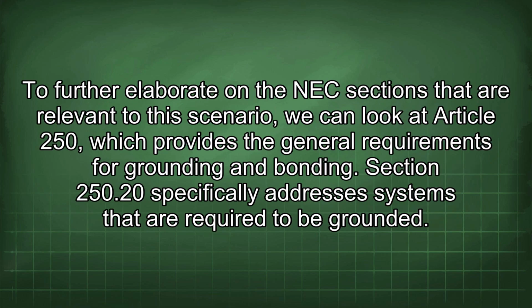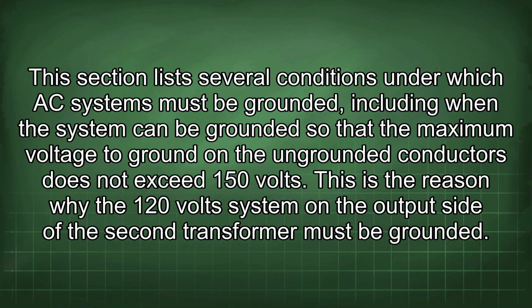To further elaborate on the NEC sections that are relevant to this scenario, we can look at Article 250, which provides the general requirements for grounding and bonding. Section 250.20 specifically addresses systems that are required to be grounded. This section lists several conditions under which AC systems must be grounded, including when the system can be grounded so that the maximum voltage to ground in the ungrounded conductors does not exceed 150 volts. This is the reason why the 120-volt system on the output side of the second transformer must be grounded.